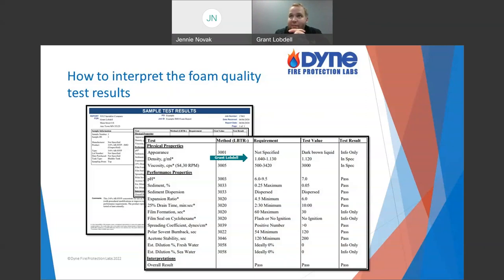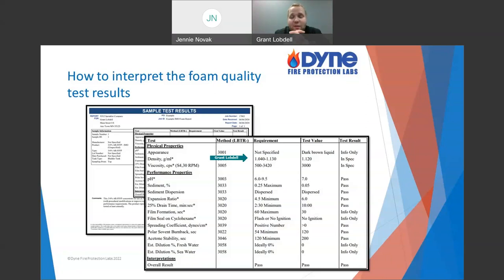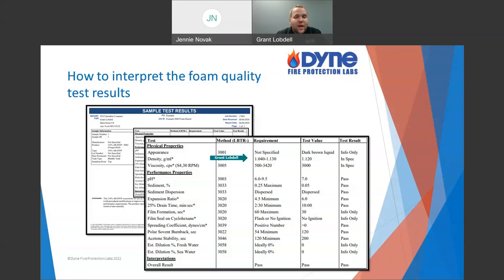What if density is high? That's very unlikely but could be some contamination, or more typically it suggests a different product than what you thought. Maybe records say one product is in there, but somewhere along the years someone put something else in or topped it off with a different foam. We can't add water and go higher — we can only dilute with water and go lower, since water's density is only 1. So high density usually means a different product.